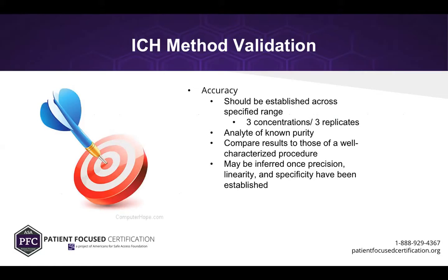So in that essence, when you're buying a standard, it should come with a certificate of analysis. That company that is manufacturing it should have a developed method to determine the concentration of the standard that they're giving you, so that you can compare the results from your analysis to that of the certificate of analysis and ensure that your instrument is reading your standards correctly.